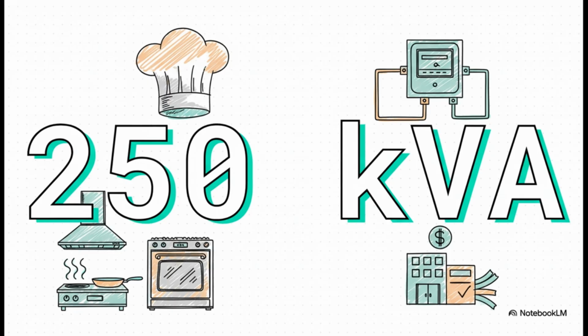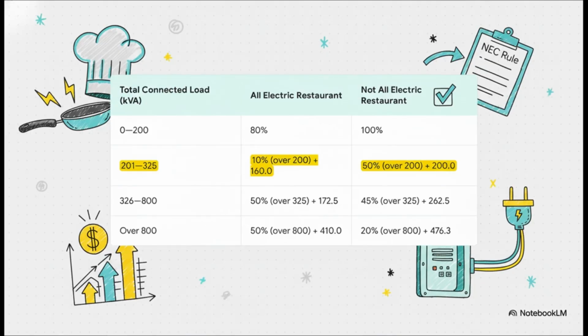Once you know your total kVA and which column applies, you pick the one calculation rule for that row. Multiply your total connected load by the demand factor, or use the specific formula given. That result, that's your final calculated load for the service or feeder. Right, so it all hinges on that all-electric versus not all-electric choice. Let's break that down. The code is essentially applying different diversity factors based on the fuel source, isn't it? Pretty much. It's reflecting decades of data on how likely equipment is to run simultaneously.